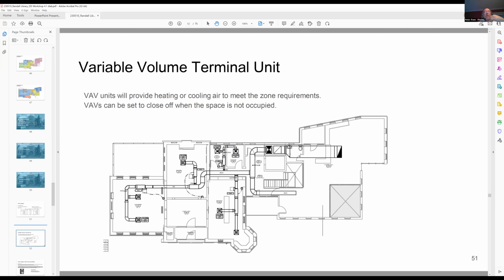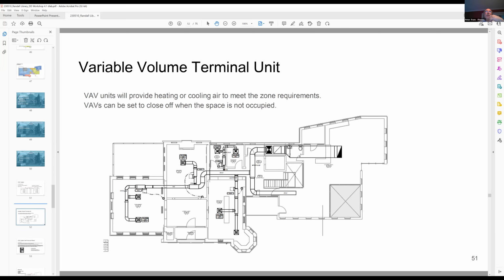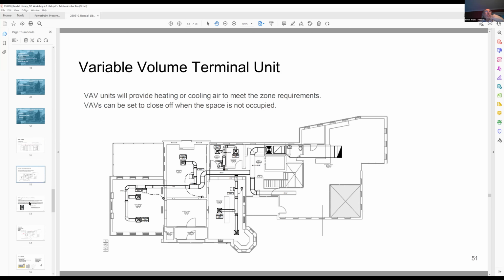So, for example, we have some open office spaces and some meeting rooms. In a meeting room that is primarily used, on occasion we have 2 people in there, and we may have 20 people in there. By using a variable volume control device, we're able to regulate that air to meet the demand of the amount of people within the space. That's been proven to be really energy efficient. If your zones are closed off and you want to shut the boxes off completely, you're able to do that, and every one of them will have a thermostat, so you can set and regulate the temperature. Some of the offices, we don't give everybody an office a thermostat. We like to group multiple offices in, and we'll always ask the folks who gets a thermostat. Most of the time it's by seniority. So when the question comes around, feel free to chime in and tell us you'd like to have the control over that.